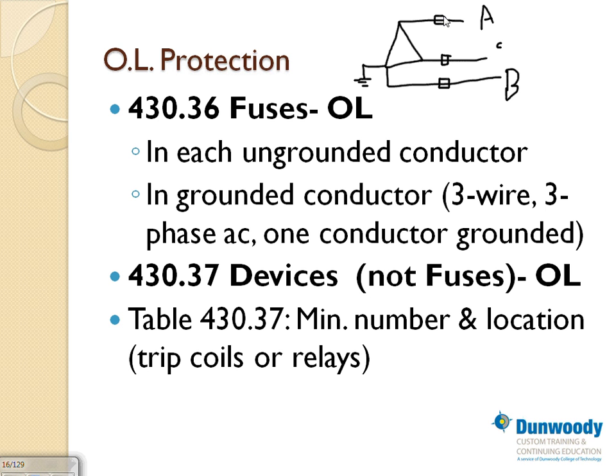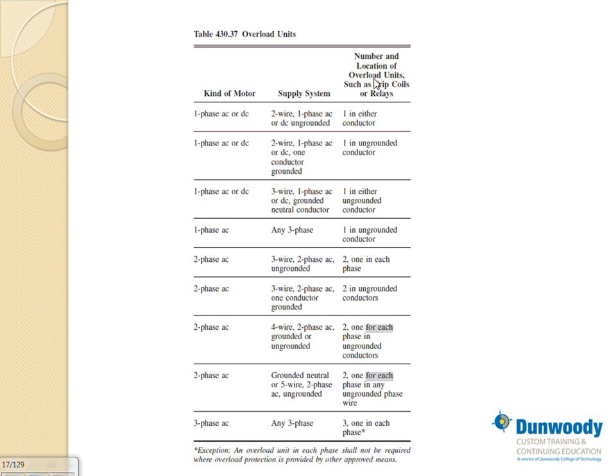If you're not using a fuse, there is a table that tells you, most of the time, in every phase we're going to use it. For example, you have one phase. It will tell you the number of conductors that we're going to use: 2-phase system, 3-phase system. You guys are going to be right in here most of the time. It tells you which system. Most of the time you're in a supply system. I have a 3-phase AC system, and any 3-phase voltage, meaning 208/120, 480/277, 240/120 3-phase, and you need one in each phase. Any questions about that? That's if you have a separate heater or a separate electronic device, not a fuse.